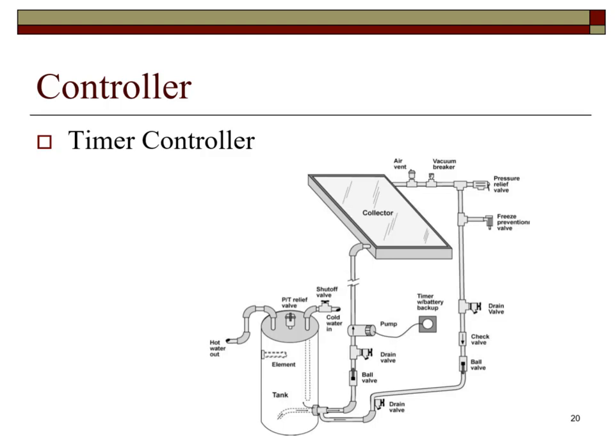This control method is used in tropical climates where temperatures are mild year-round and significant amounts of solar energy are available almost every day. In a timer controller system, a timer turns on a pump in mid-morning and switches it off in late afternoon. To ensure that the heated water stratifies to the top of the storage tank, the system uses a very small pump. The collector feed and return lines are both connected through the use of special valves at the bottom of the storage tank, so only the coldest water from the tank flows through the solar collector.